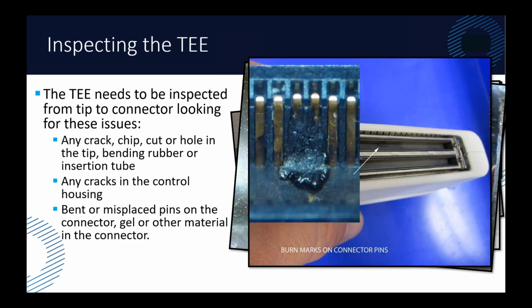This is an example of what can happen if water gets on the wrong two pins on a connector. This can even happen with non-TEE probes. A little bit of gel gets in there. I actually had a sonographer one day do $25,000 worth of damage because that happened. She was one of the best sonographers I've ever worked with as far as having her house in order, very specific, but she just touched the probe and didn't realize she had gel on her finger. It was in there, she plugged it in. She actually told me she heard it sizzle. And when she heard it sizzle, unfortunately, she switched probes and cross-talked all the high voltage to the other probe and killed it too. I'm like, you should have just unplugged it. But, you know, things happen.